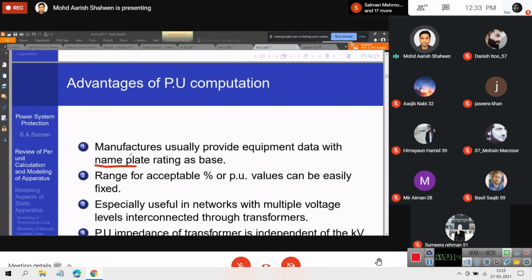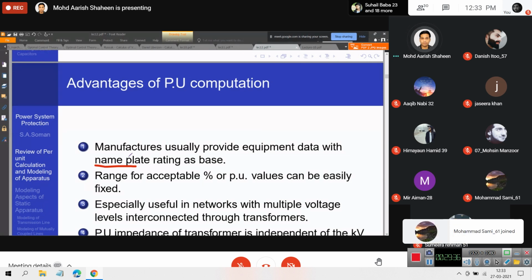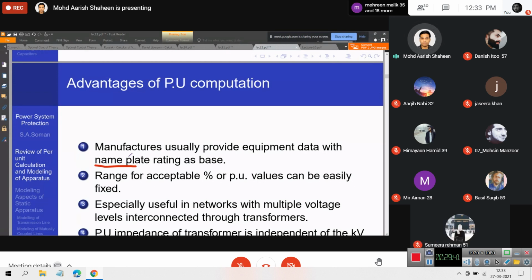It is basically the high voltage side rated voltage, low voltage side rated voltage. The rated megavolt amperes, that is to say the power rating of the transformer, the apparent power rating, the efficiency of the transformer. It can also list, say, the series impedance voltage, which you obtain from the short circuit test. It can also give some indication of the open circuit test data as well. The rated temperature rise, the kind of oil that is used, the weight of the transformer, the dimension of the transformer, anything electrical as well as non-electrical information can be obtained from the nameplate.